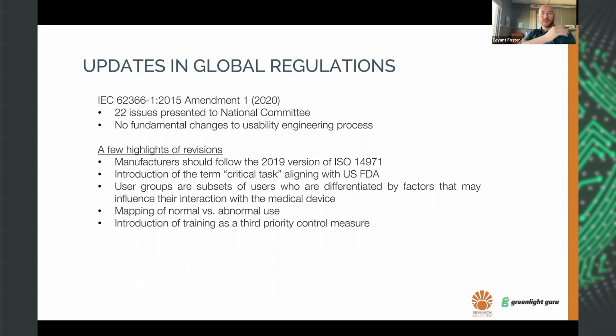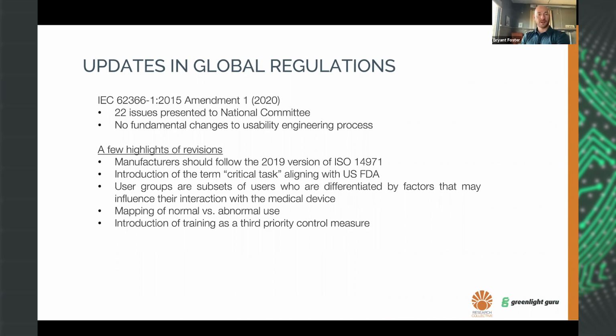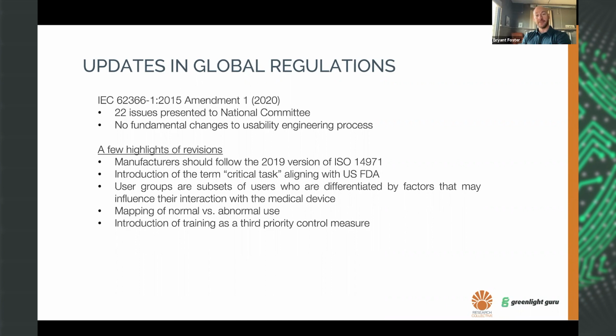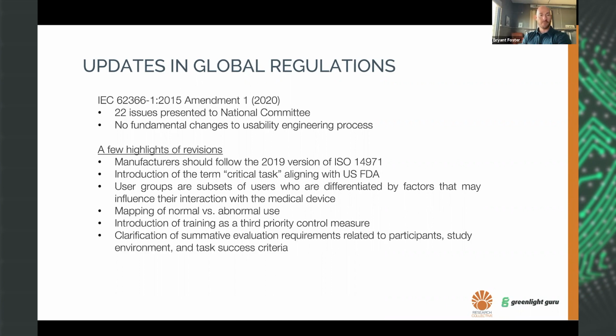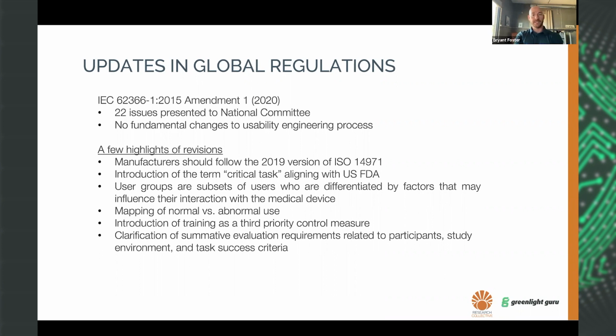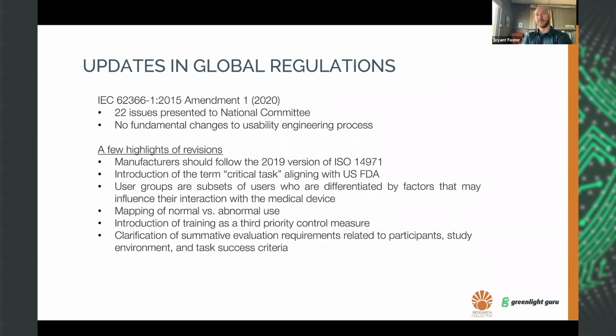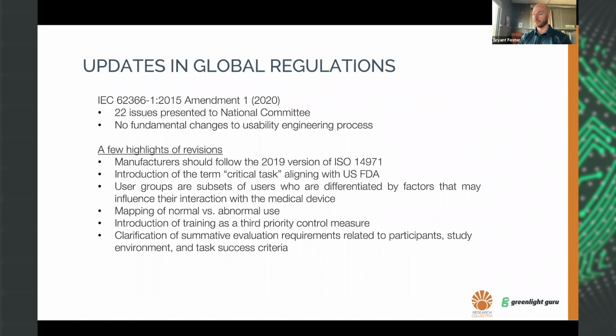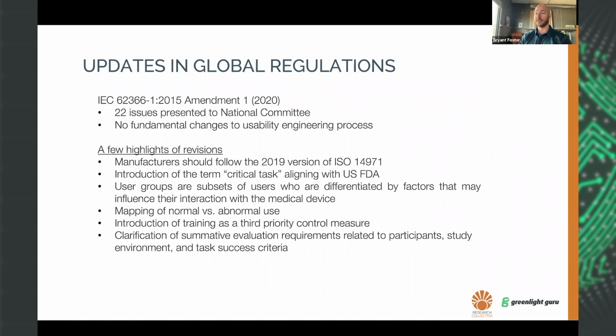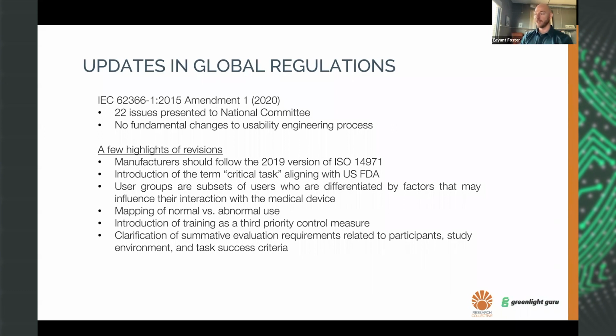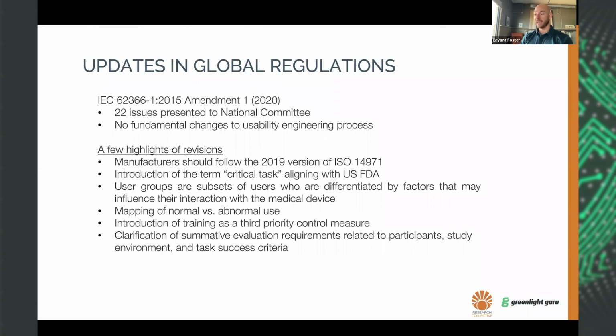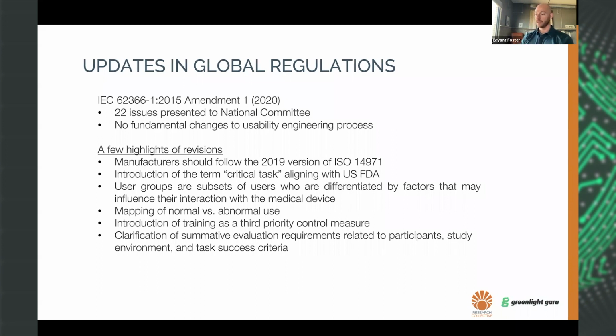Next, introduction of training as a third priority control measure. So just like your labeling, instructions for use, training is a part of the user interface. This isn't new, again, but it just adds that clarification. Further clarification of the summative evaluation requirements related to participants, study environment, and task success criteria. So, it explicitly states how participants in the summative evaluation should represent the intended user profiles, describing how the test environment and conditions of use adequately represent the intended use environment, and then defining correct use for each hazard use scenario.